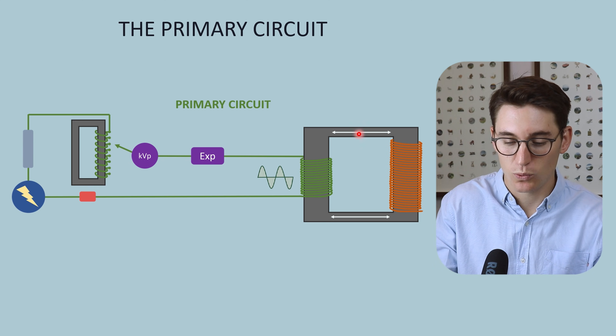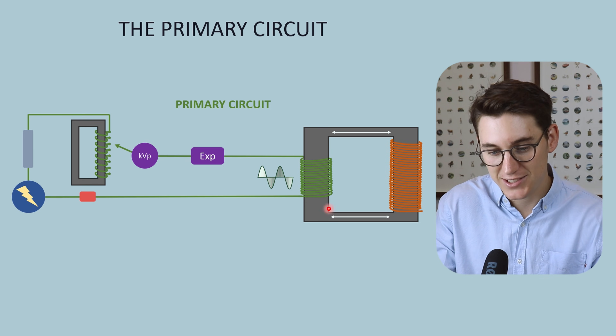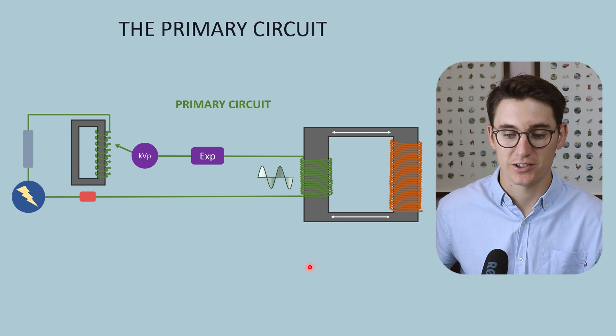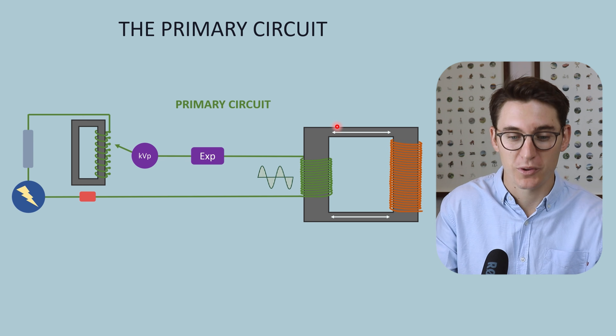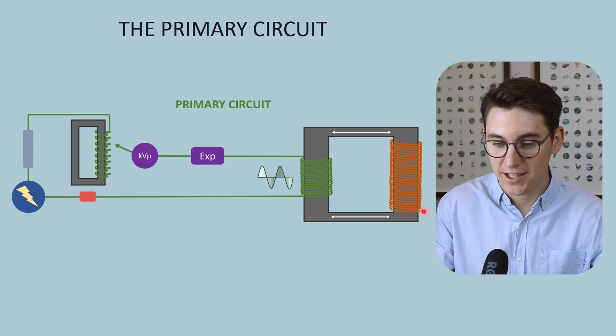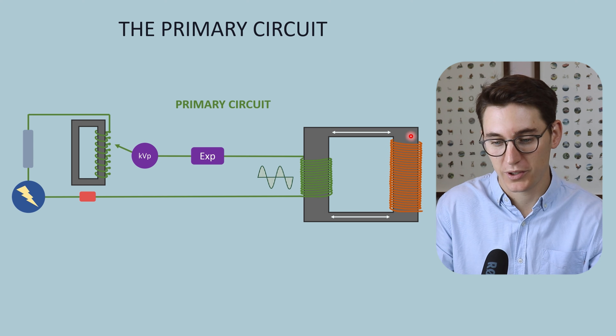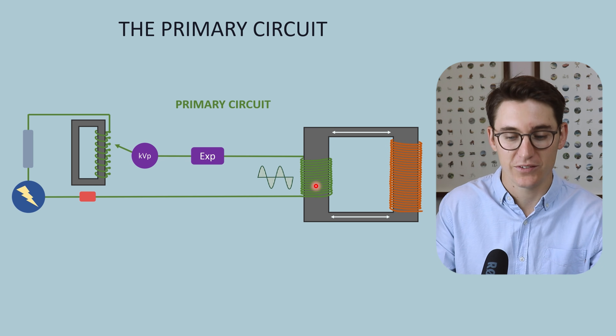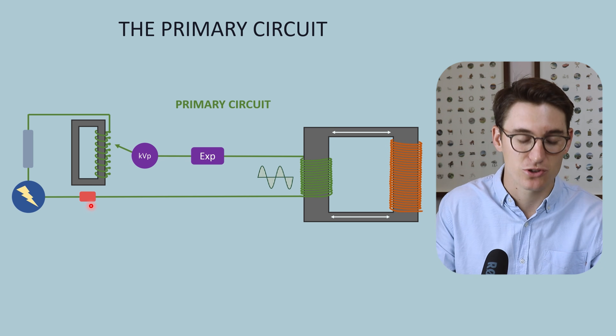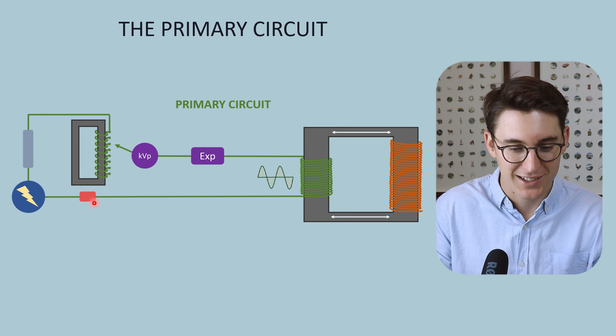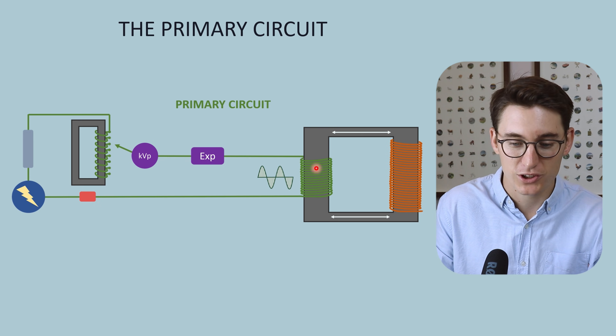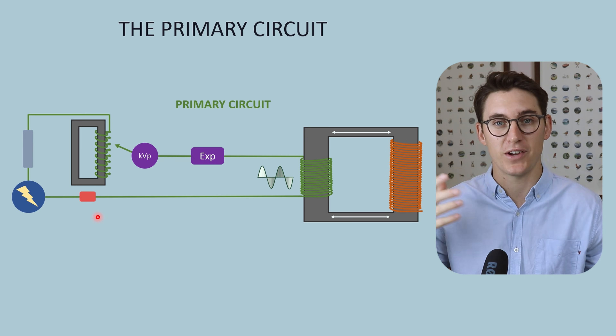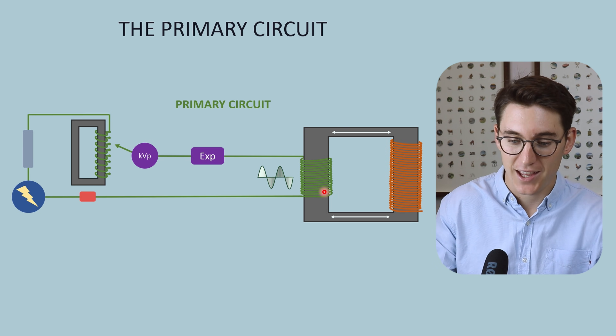The voltage then heads into the step-up transformer, which brings our low-voltage current up to high voltage. The first half of the step-up transformer forms part of the primary circuit and the second half forms part of the secondary circuit. Before leaving this image, I want to mention the circuit breaker — a safety mechanism that acts essentially as a fuse box, breaking the circuit if voltage is too high to prevent x-rays with energies that are dangerously elevated.